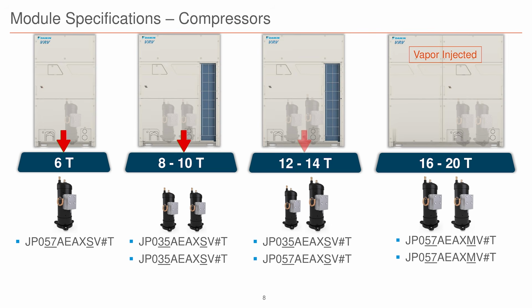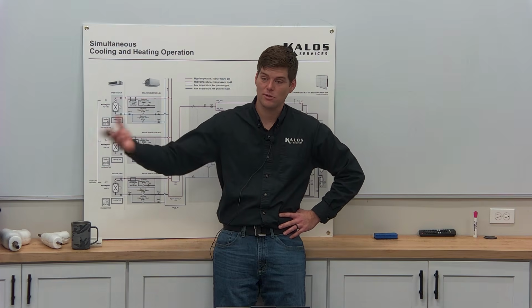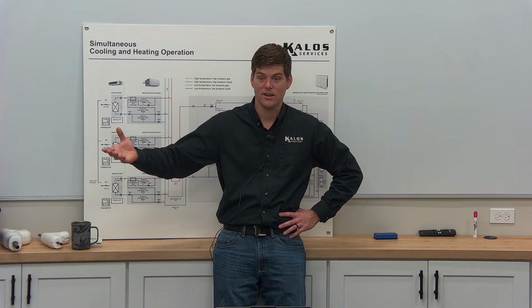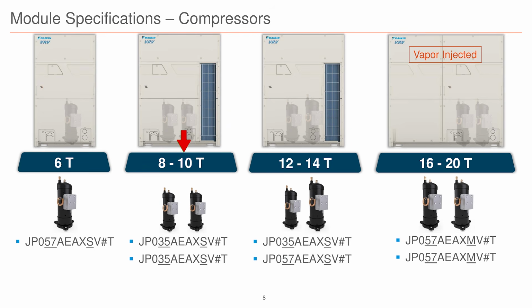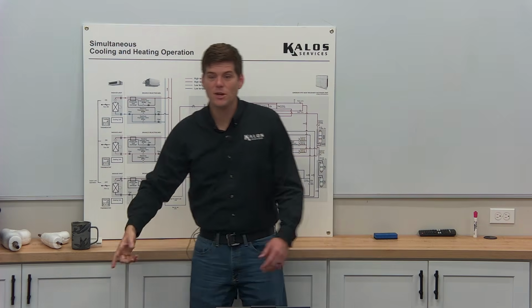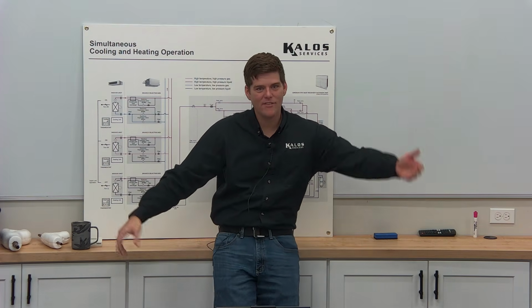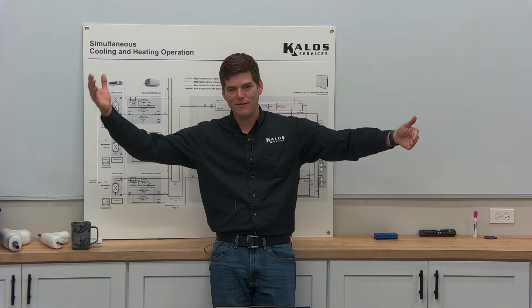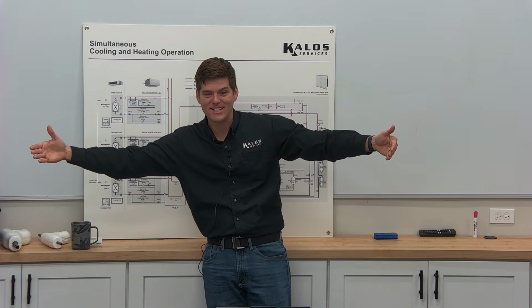8 to 10 ton, 12 to 14 ton, 16 to 20. And I say 4 different sizes. They're actually sizes inside of the sizes themselves. The cabinets don't change. It's just a matter of compressor speeds and fan speeds, right? So you'll find that the 8 to 10 ton cabinet looks just like the 12 to 14 ton, but you'll notice it has one bigger compressor. You see that on the side there? And you say, well, how is that possible? How do we have an 8-ton unit and make it produce 14 tons of capacity?